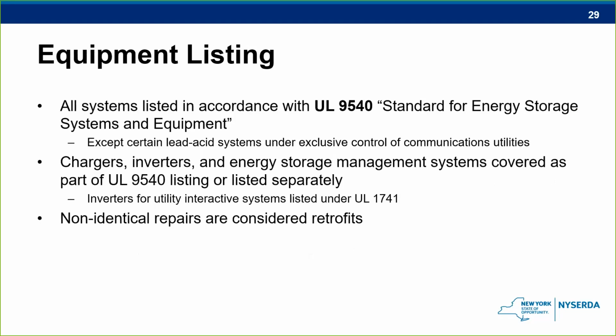And to further safeguard against some of those hazards that I mentioned earlier, systems must also all be listed in accordance with UL 9540, which is the standard for energy storage systems and equipment. Chargers, inverters, and battery management systems, if they're not already covered as part of that system UL 9540 listing, can be listed separately. And it's important to note that if systems are repaired with anything other than identical parts, it'll be considered a retrofit, subject to a permit application and most of the same requirements as a new system.